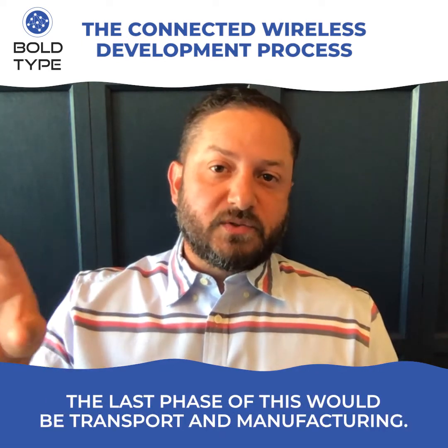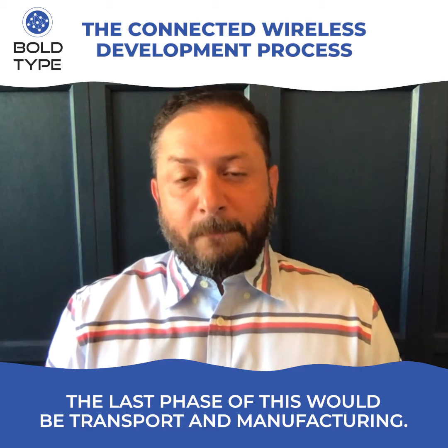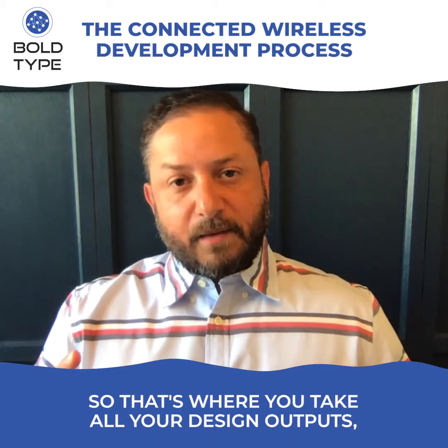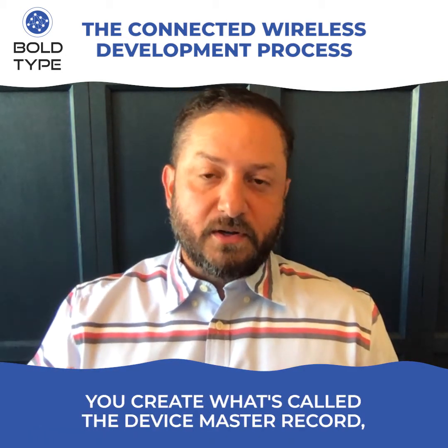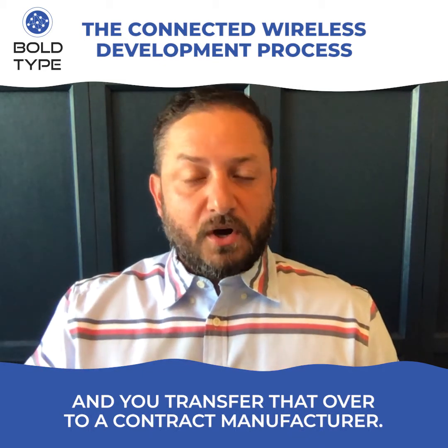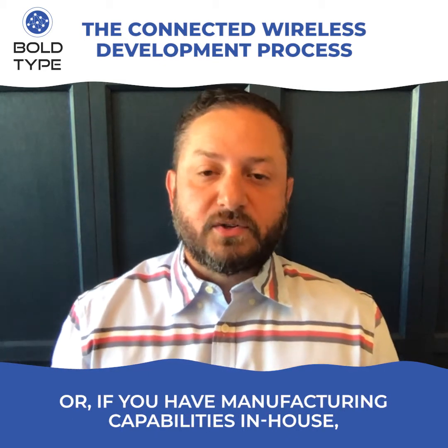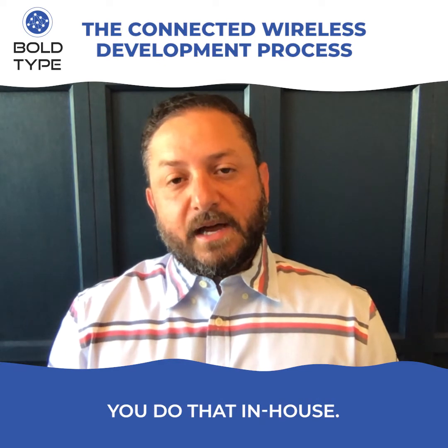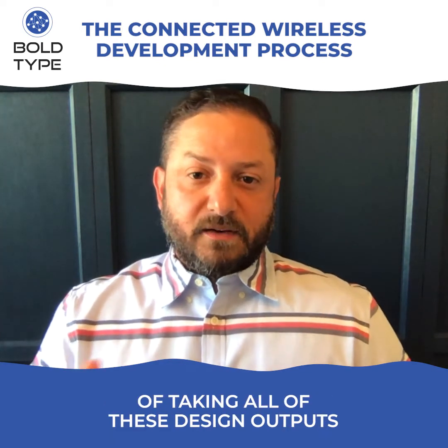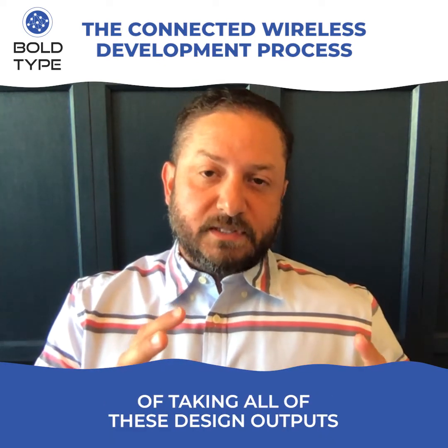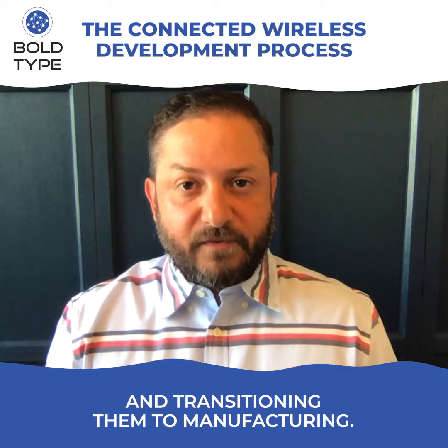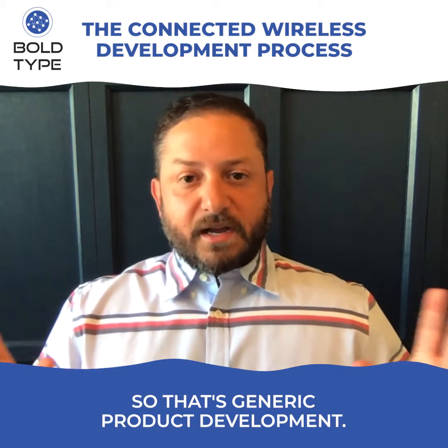The last phase of this would be transfer to manufacturing. So that's where you take all of your design outputs, you create what's called a device master record, and you transfer that over to a contract manufacturer, or if you have manufacturing capabilities in-house, you do that in-house. But you go through that whole process of taking all of these design outputs and transitioning them to manufacturing. So that's generic product development.